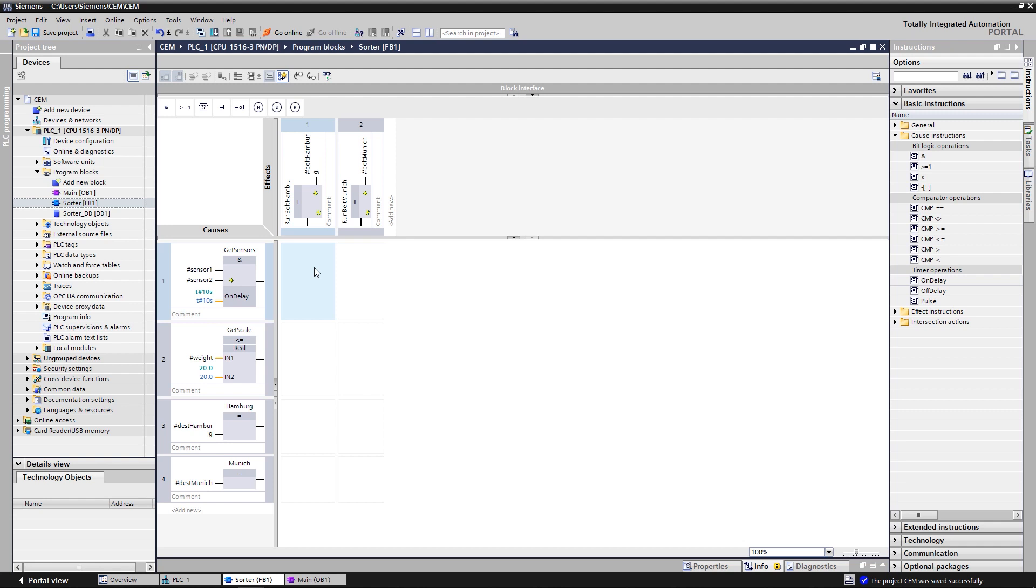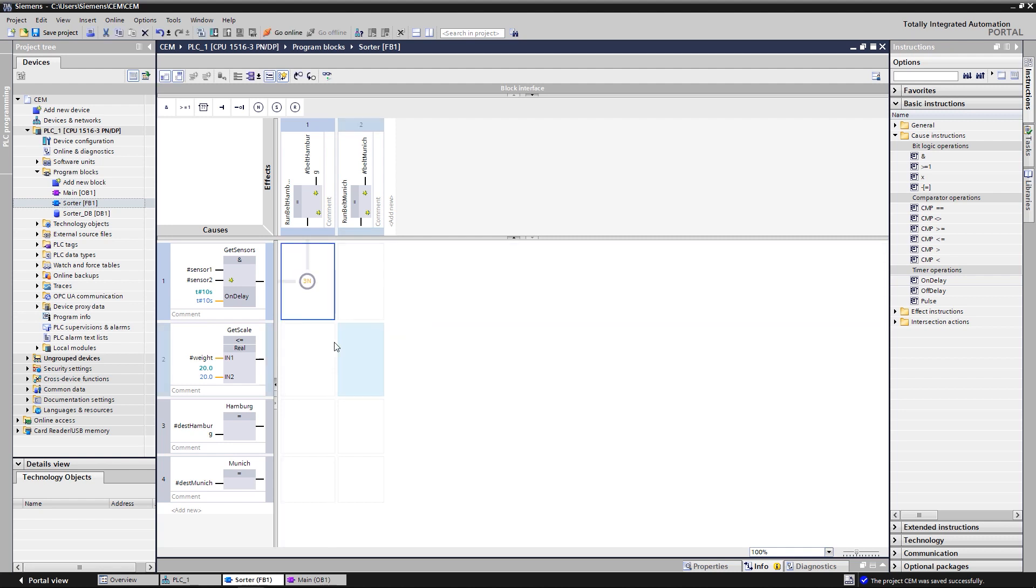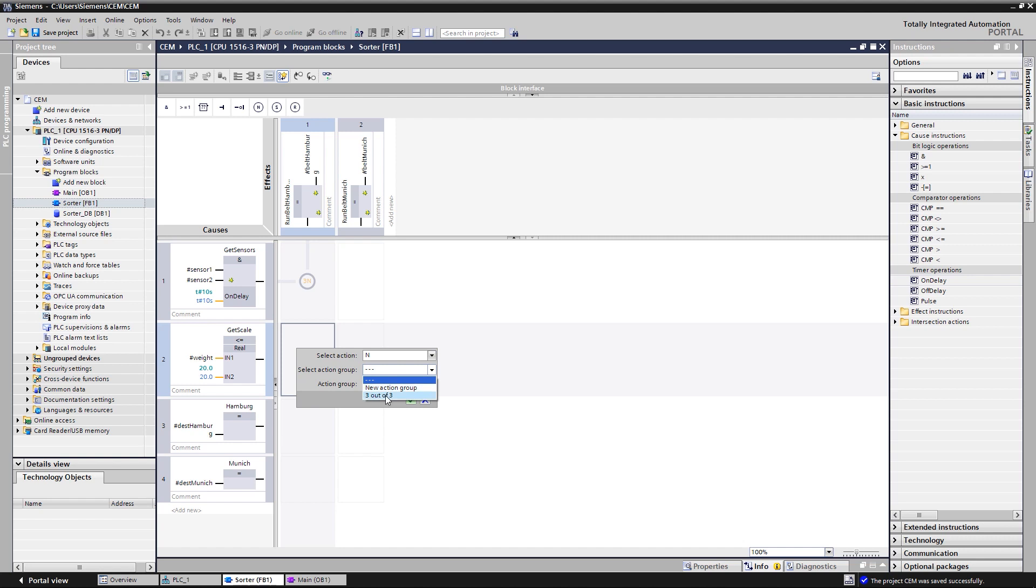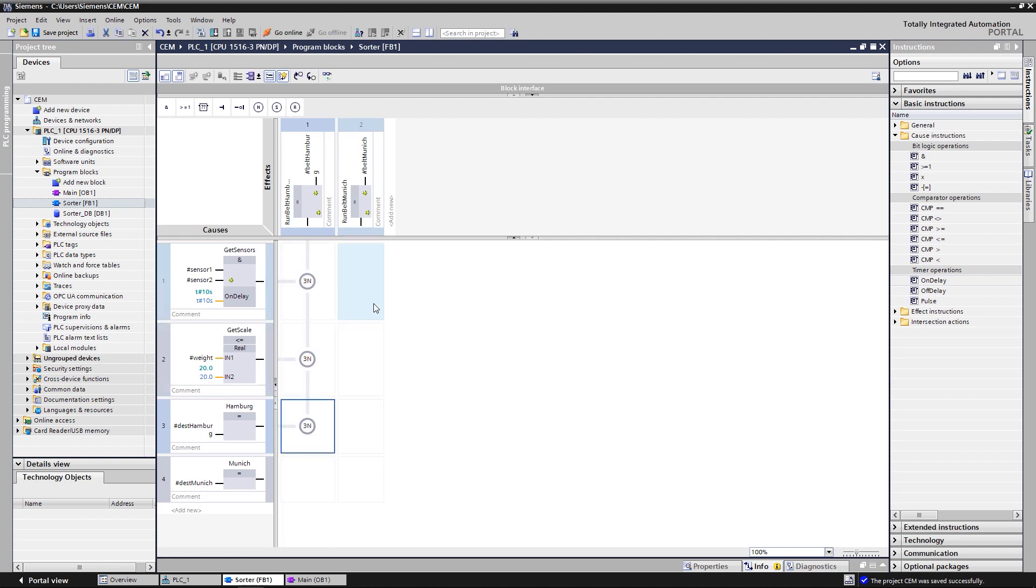However, in order tasks, the effects must only be executed if all the three conditions are satisfied. For this, the action group was implemented in CEM. Combine all the three actions of the column in a group. The number indicates that all the three actions have to be active for the result of the group to be true, so that the associated effect is executed.